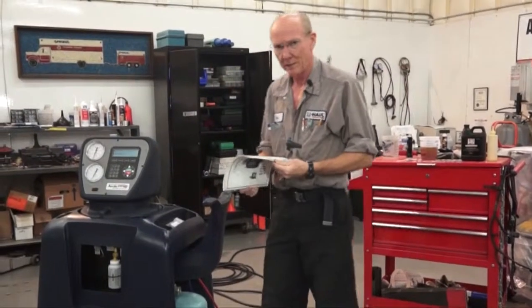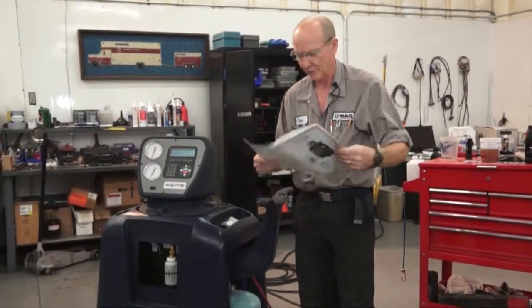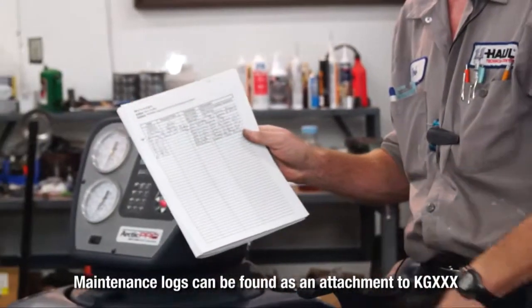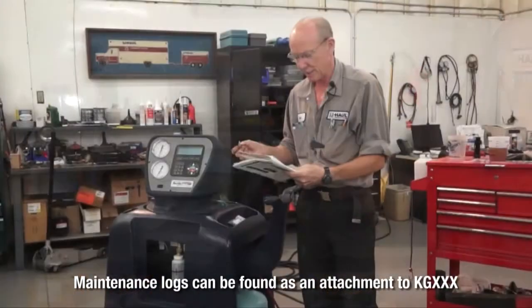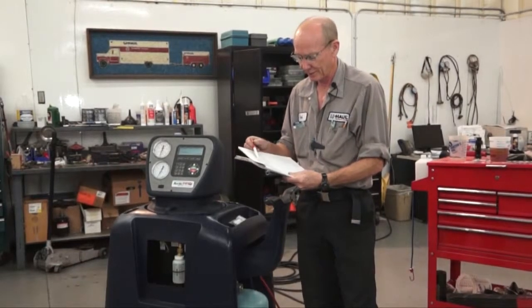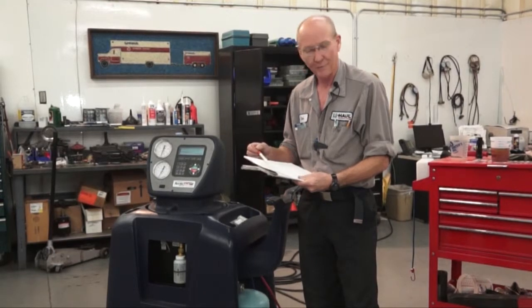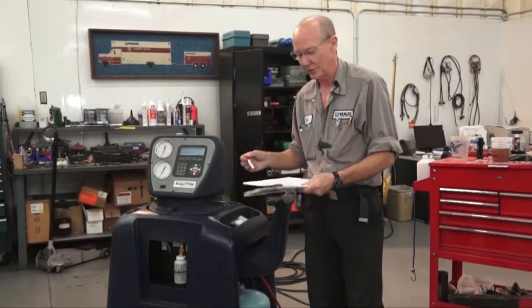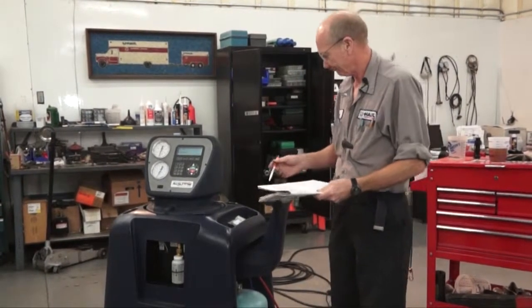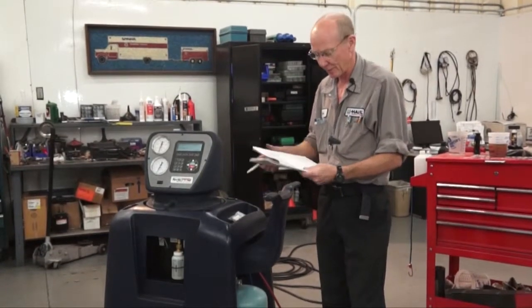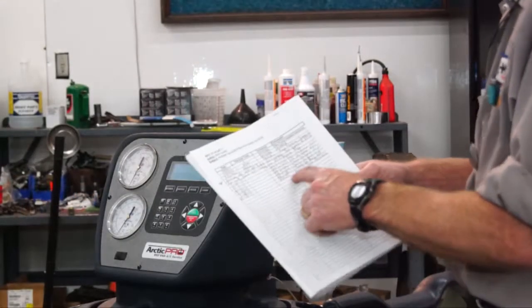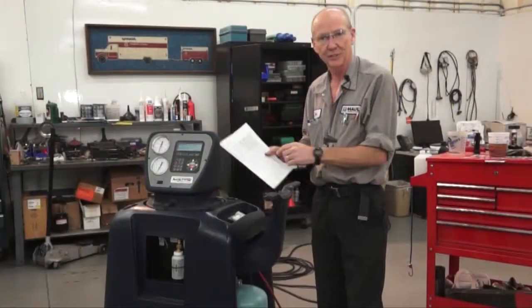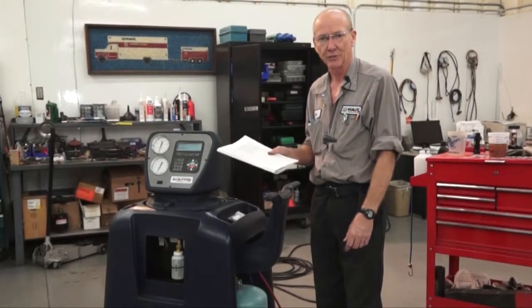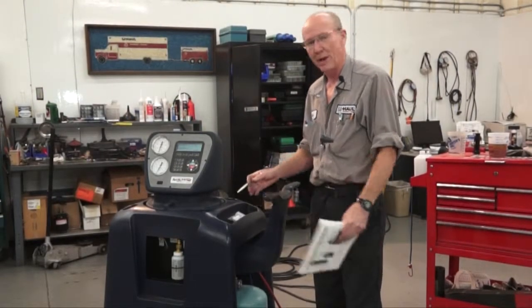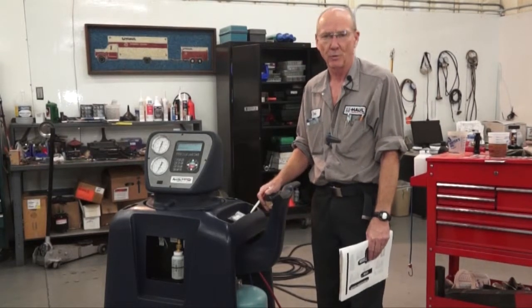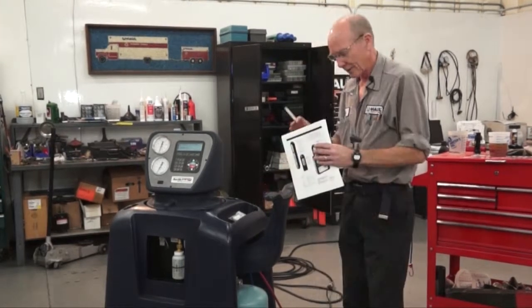I like to keep track of every time I perform a service on this, so I made myself a little sheet that I stapled to the inside back cover. I have the date, the technician, which is me, and comments, whatever you do to the machine, whether you calibrate it, change the inline filters, or change the vacuum pump filters. I always date it, put my name and what I did. It just helps you keep track of the maintenance on this machine, and if you ever do have a breakdown, it really helps with warranty as well. And that should be about it.